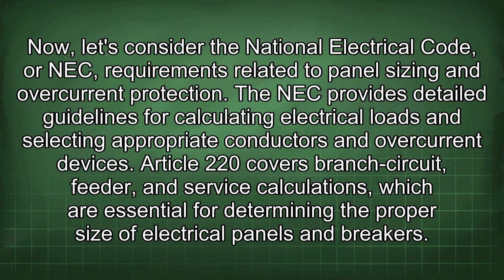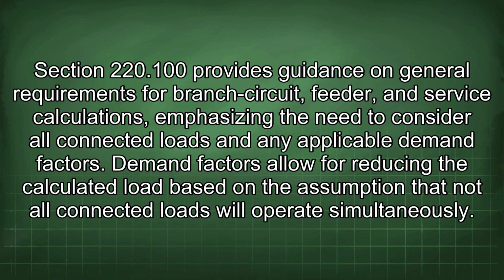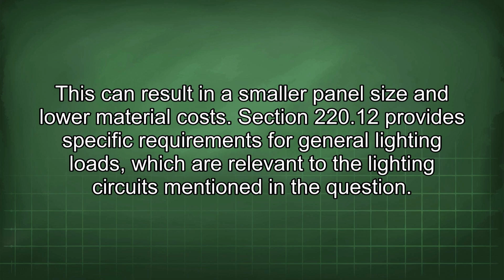Now let's consider the National Electrical Code, or NEC, requirements related to panel sizing and overcurrent protection. The NEC provides detailed guidelines for calculating electrical loads and selecting appropriate conductors and overcurrent devices. Article 220 covers branch circuit, feeder, and service calculations, which are essential for determining the proper size of electrical panels and breakers. Section 220.100 provides guidance on general requirements for branch circuit, feeder, and service calculations, emphasizing the need to consider all connected loads and any applicable demand factors. Demand factors allow for reducing the calculated load based on the assumption that not all connected loads will operate simultaneously. This can result in a smaller panel size and lower material costs.